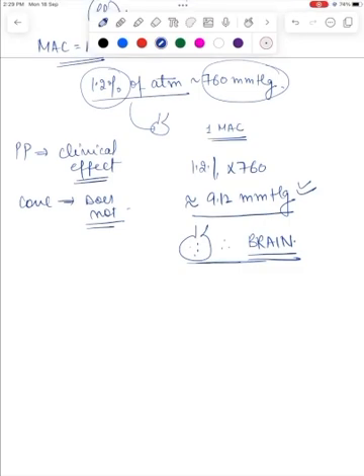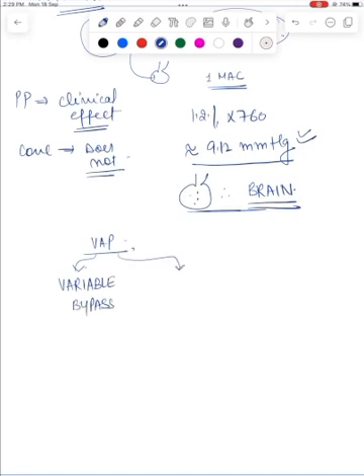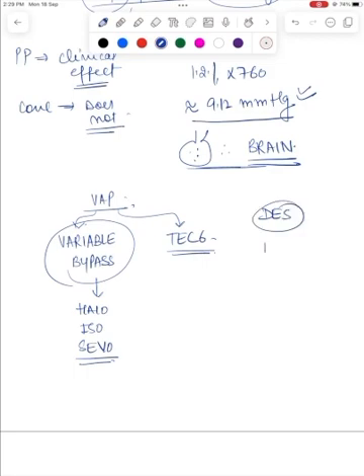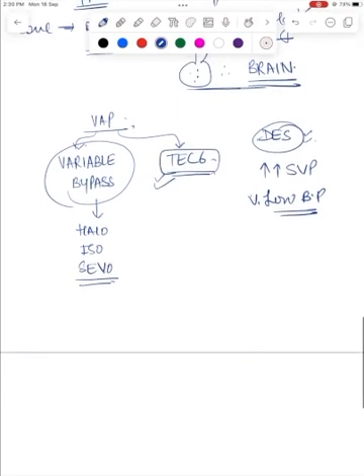The vaporizers commonly used in clinical practice can be variable bypass vaporizers, and there is also the Tec 6 vaporizer. Variable bypass vaporizers are used to deliver halothane, isoflurane, and sevoflurane. Desflurane, because of its very high saturated vapor pressure and very low boiling point, cannot be used in a traditional variable bypass vaporizer. Therefore it needs a specialized vaporizer of its own — one example of a specialized desflurane vaporizer is the Tec 6 vaporizer.